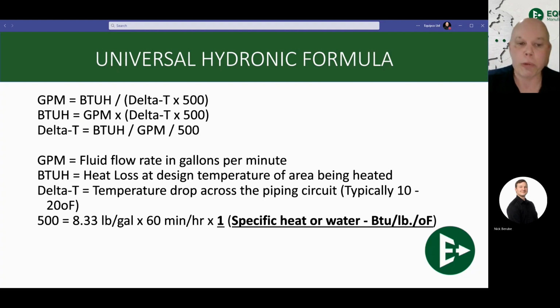So there's why we had to change that mathematics, to convert from pounds into gallons. So you have 8.33, which is 1 gallon, times 60 times 1, 1 being the specific heat carrying capacity of water. So you can do that 8.33 times 60 times 1. I think the number is 499.96 or something. If you're at home, try it. It'll be a great time. Now, the 1 changes depending on the water. And the water is not always 100% water. Sometimes it's a glycol mix, and that's where that 1 is going to change.